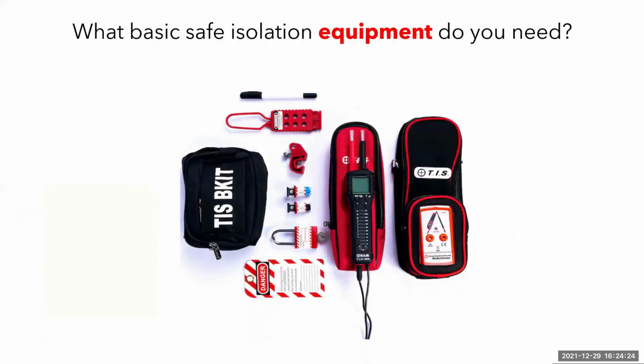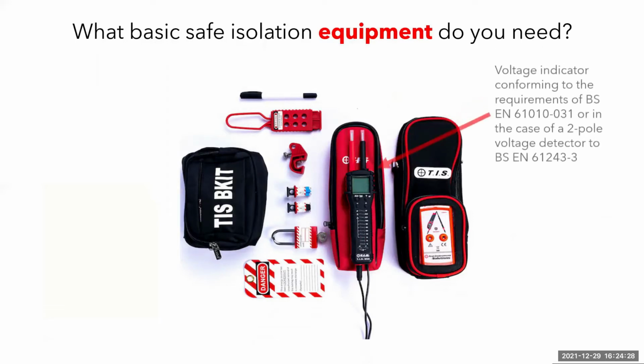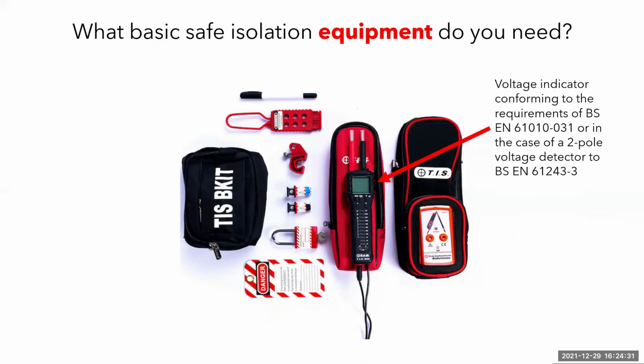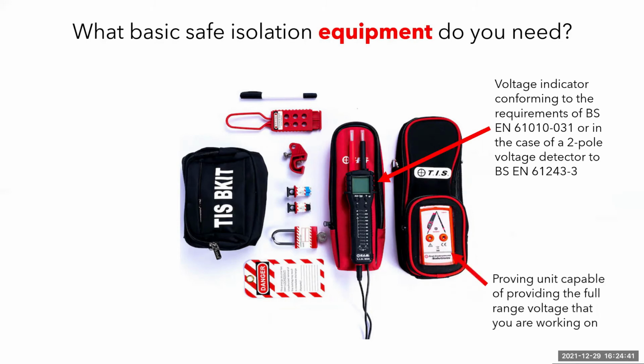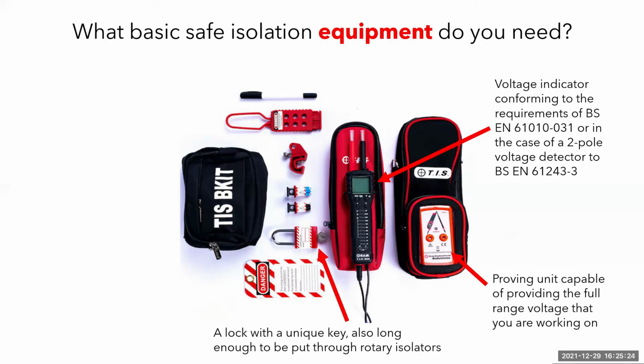Here is an example of a basic safe isolation kit. This kit comprises a voltage indicator complying with BS EN 61010-031, or in this instance, BS EN 61243-3, a proving unit capable of showing the full range voltage for the circuits that you are working on, and a lock with a unique key that only you have access to. Try and get a long one like this, as it will be long enough to fit through rotary isolators, etc.